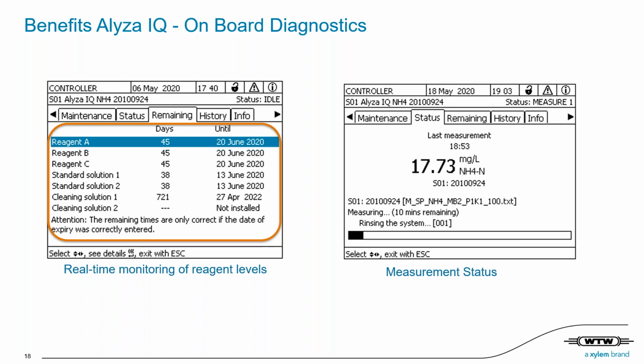To guarantee highest performance stability and reliability of the data, additional functions like temperature within the different compartments, as you've seen, for example, 20 degrees for the wet chemical unit, are continuously monitored and displayed in the info screen. For full transparency, we also optimize the status screen within the controller. You can see the latest measurement and the current process stages of the next measurements. So in that case, the last measurement took place at 6:53 p.m. and a concentration of around 17 milligrams per liter ammonium.